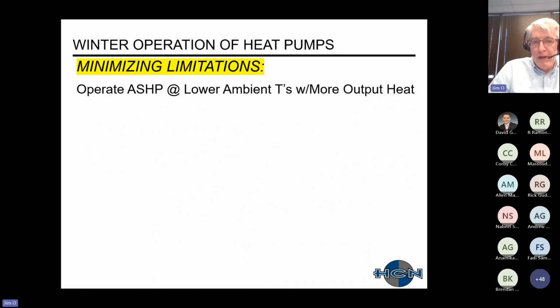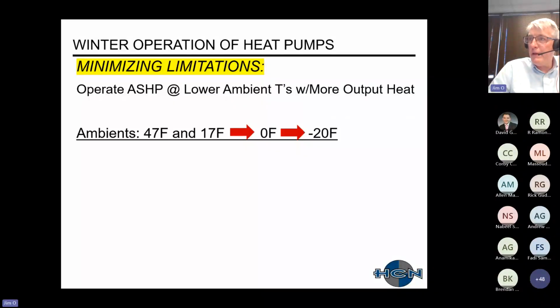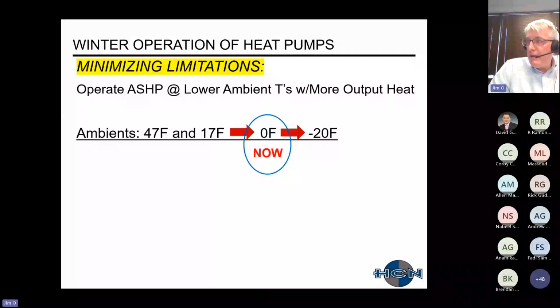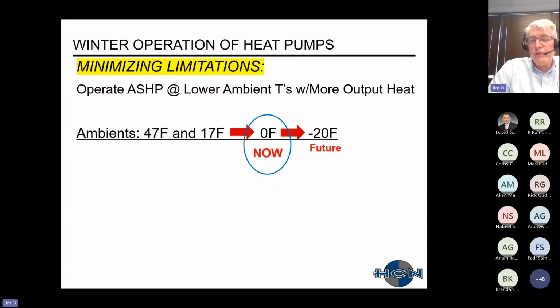So let's talk about how the manufacturers or designs are trying to minimize the limitations of your heating capacity as well as your defrost. What they're trying to do is operate your air source heat pumps at lower ambient temperatures, producing more output heat. So currently the design, I'll say, is averaging about 0 degrees for ambient. In the future, they are working towards minus 20 ambient.